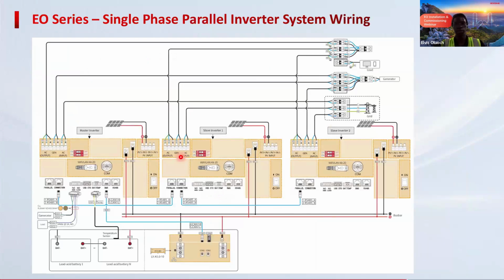Next, we'll be looking at paralleling. For paralleling, the sequence is the same as a single inverter. The main difference will be that in case you're using lithium, we would propose that you use a common bus bar for all the inverters. As you can see here, we have 3 inverters. Then if you can quickly check here on the DIP switches, you can see that on the master, which is the first inverter, it is on. On the middle inverter, it is off. And then on the final inverter, it's on. Therefore, in case you had 2 inverters, that means both of them will be on. So for the first and last inverter, on.